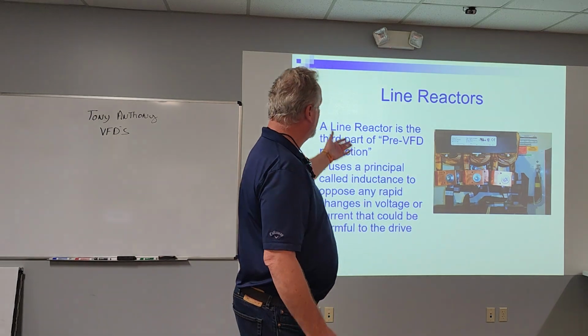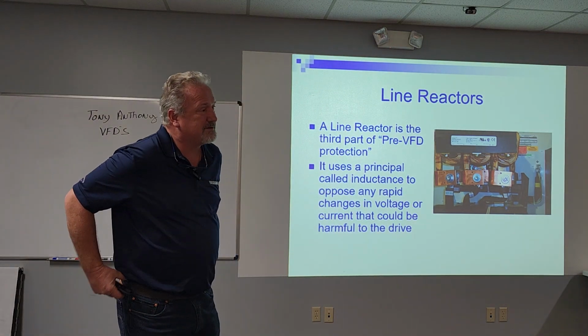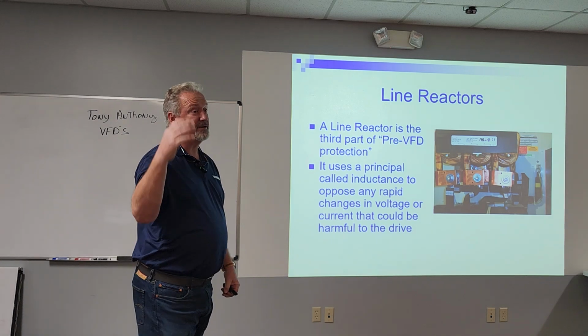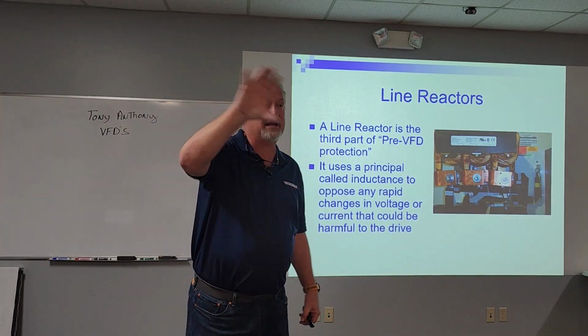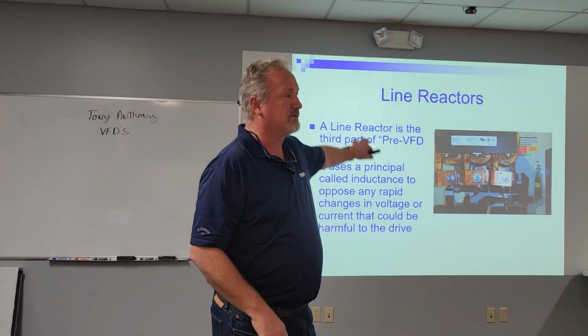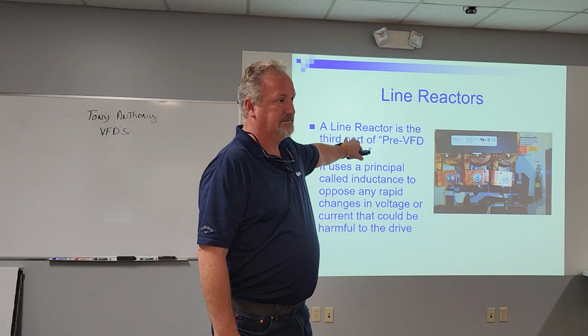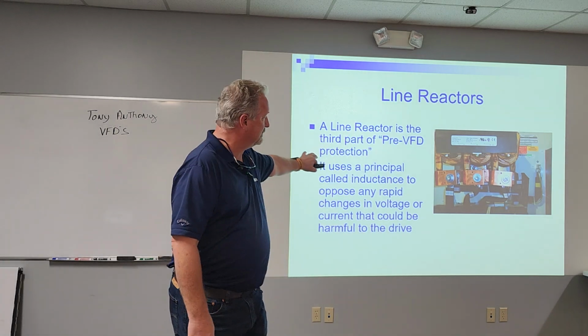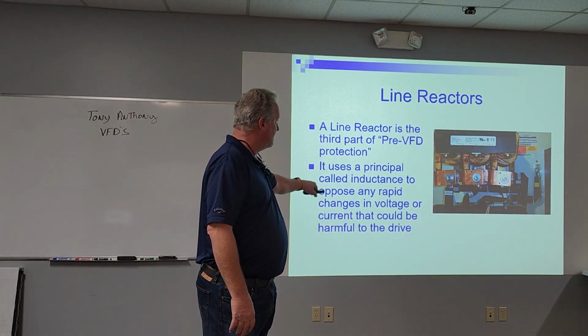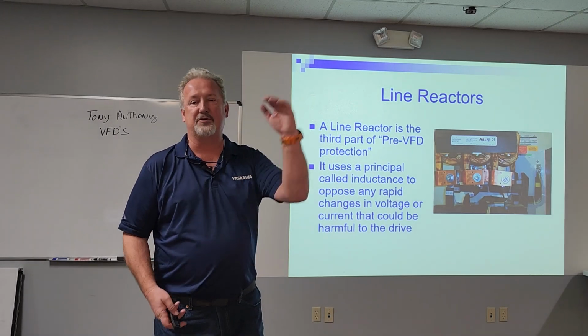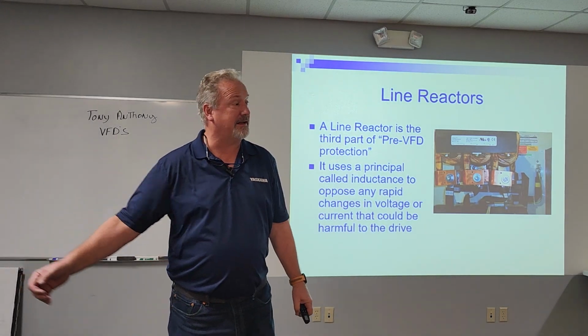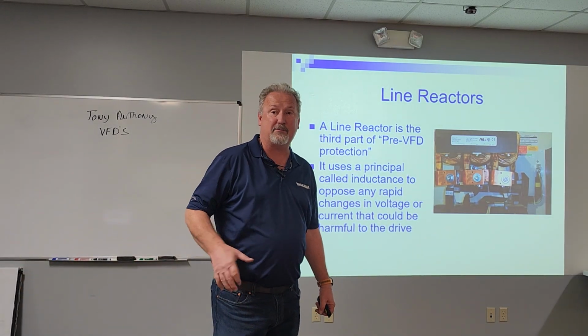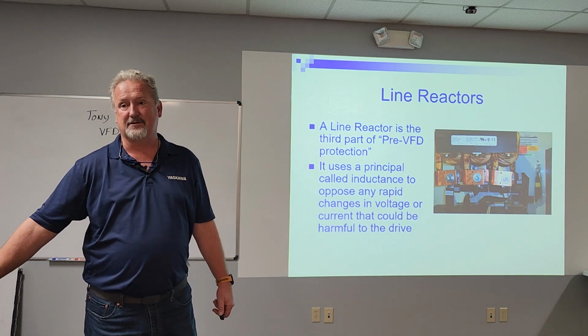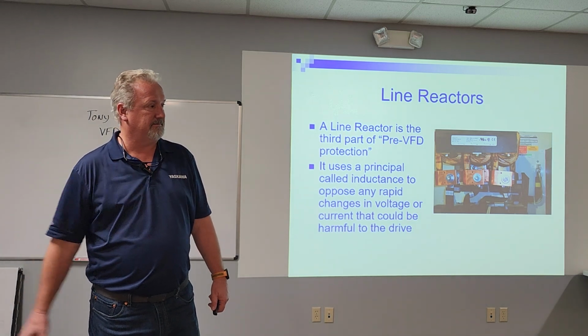I said all that to say why we use line reactors. One of the biggest reasons we use line reactors is the drive distorts the harmonics on the AC sine wave 80%. This will cut it in half. And it has some other things that we'll talk about in a second, but that's the biggest reason we use it, to reduce that harmonic. So like I said, now instead of 90 people topping off their tank, we just cut it down to 45. So we're further from having troubles.